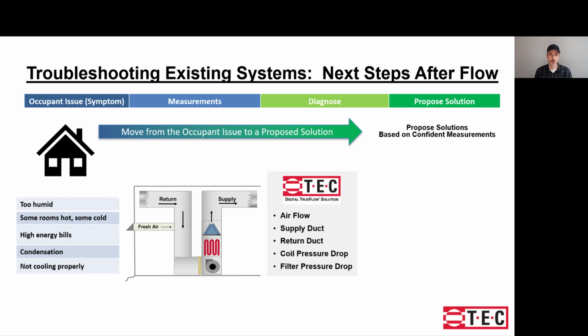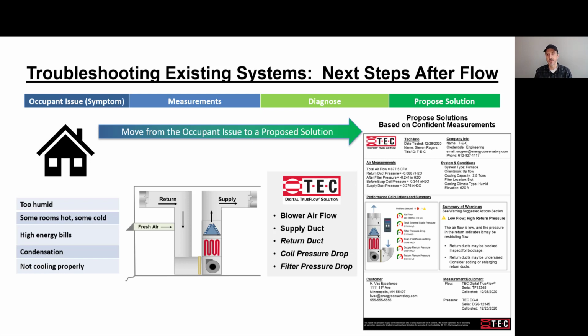And that's what the digital TrueFlow solution tries to support. You can certainly do these measurements without this solution. This solution will help you make those measurements in a consistent way, make accurate measurements, and then gives you a report that summarizes all of your measurements, but also helps give you a start on the diagnosis of what you'll see. In this example, there was a lower flow reading and a higher return duct pressure, and based on the combination, it's suggesting that looks like you have some return ducts either blocked or undersized, and that would be a good thing to do to increase the airflow and address perhaps this comfort issue.